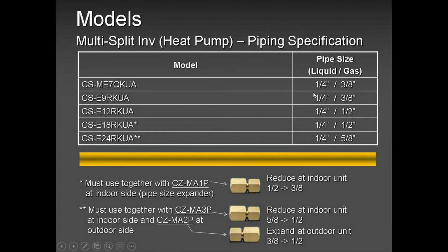Now, guys, this is very important. If you are using multi-zone, in most of your jobs, this slide is very, very important. Unlike our competitors, who bring the indoor unit pipe size all the way to the outdoor unit and do all the adjustments at the outdoor unit, meaning they use a reducer or an expander, in our case it's different. In our case, all the ports, whether 2, 3, 4, or 5 depending on the multi-zone you're using, have 3/8 and 1/4 inch pipe sizes. 3/8 suction, 1/4 inch liquid.